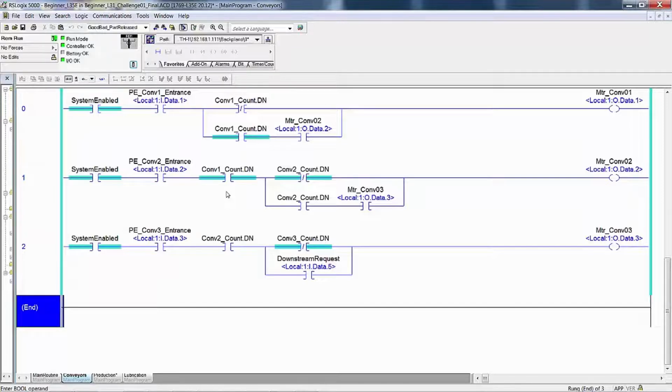And since conveyor 1 is full, conveyor 2 will have to energize to pull the part exiting conveyor 1 fully onto conveyor 2, blocking photo I2 and running until both photo I1 and photo I2 are clear. Before we go to the next paragraph here, think of this. If conveyor 1 is full, which it is right now, with 3 cartons, nothing's going to move until another carton arrives at the entrance of conveyor 1, which means that you're going to turn on input 1 first.